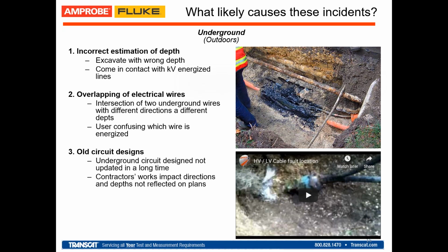This relates to the third point: old circuit designs. We've seen so many customers make contact with energized circuits because their plans are 20, 25, 30 years old. They never validated or updated them. Because of environmental situations like soil moving, or an extension done by another contractor, the depth doesn't match the plan, and they hit the utility.